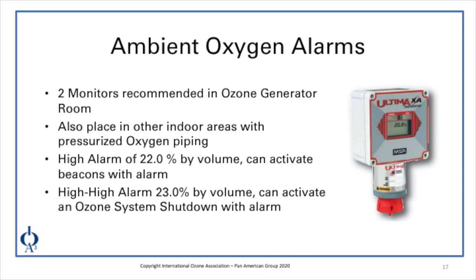Within ozone facilities, it's important to have monitors in appropriate locations to notify us in the event of oxygen leaks. The recommendation is that two monitors be placed within the ozone generator rooms and also placed in other indoor areas where pressurized oxygen piping occurs. A high alarm to indicate an enriched environment occurs at 22% by volume, which can activate beacons with alarms. A high-high alarm at 23% by volume can activate an ozone system shutdown with alarm, and typically will trigger an isolation valve to close back at the liquid oxygen storage tank.